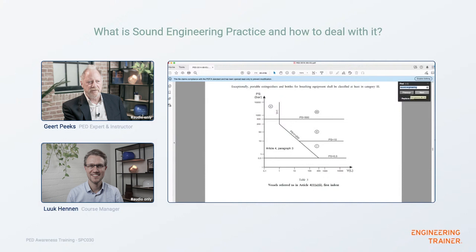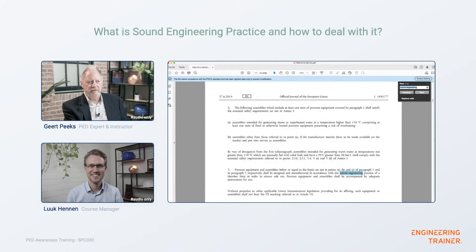If you end up in this category, the equipment should be designed and manufactured in accordance with the sound engineering practice of a member state. This is where confusion starts, as engineers typically want a design standard or framework. The term is not defined in the Pressure Equipment Directive. You have to go back before 1998 — before the PED existed. For instance, in the Netherlands you had to use the Dutch pressure vessel rules to put equipment into the market.